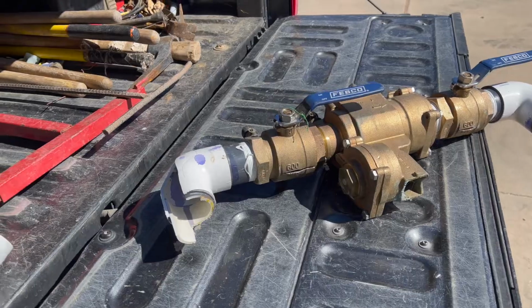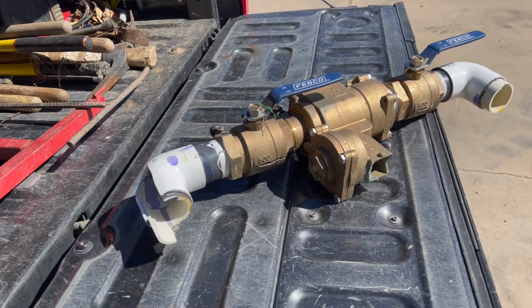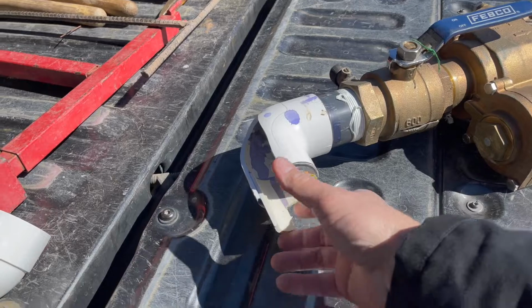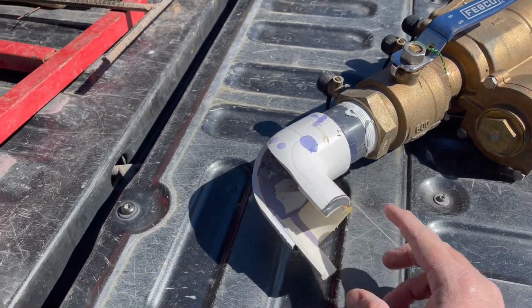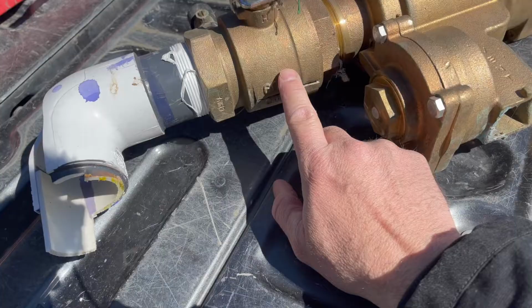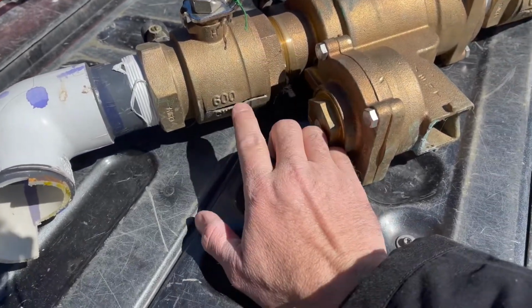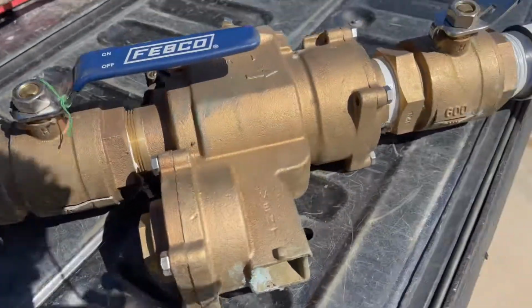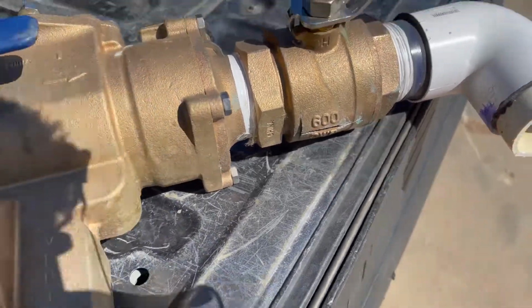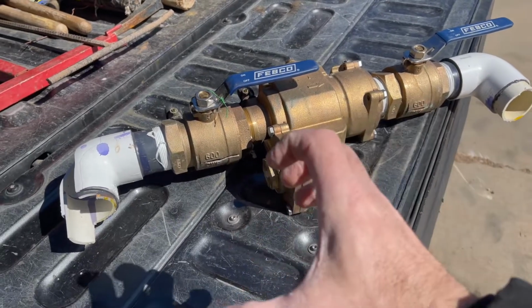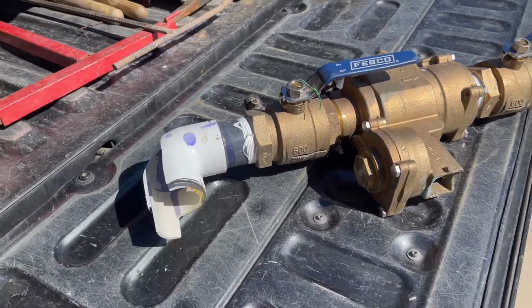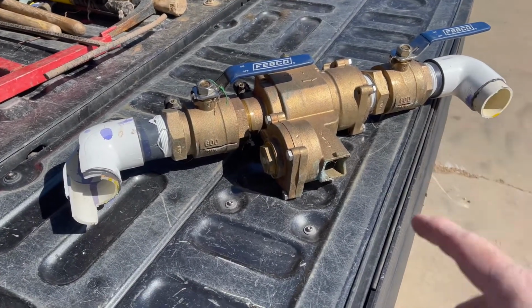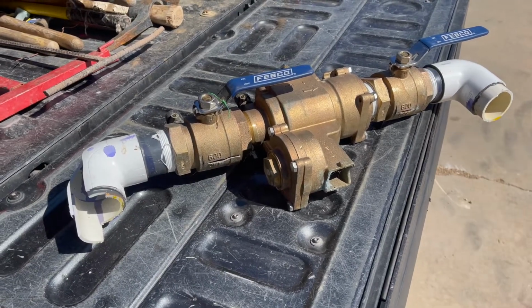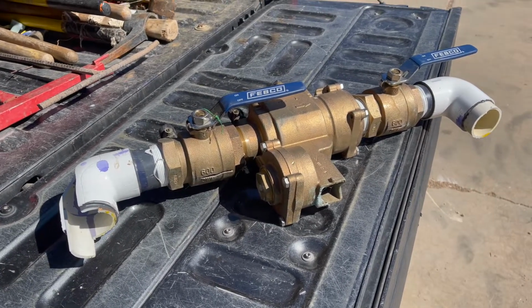Let me show you what happens when you don't insulate one and get some freezing weather. This is what happens to your backflow device if you don't drain it or get it insulated and covered up. You see this fitting, totally cracked. And the shutoff valves, the ball valves to this RPZ—you see that crack? This one cracked the exact same way. The water inside froze and expanded so much it cracked the metal part and cracked the PVC. This is a really expensive repair, something I wish we would have taken care of before the freezing weather hit.